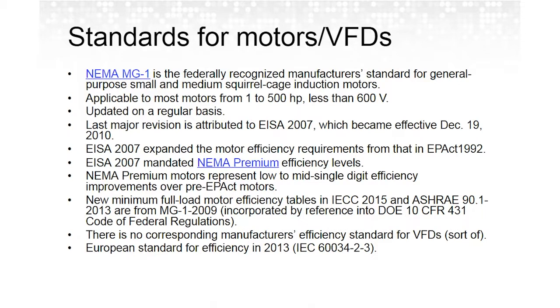Moving on to standards for motors and VFDs, let's put discussions about state energy codes aside and talk about motors and VFDs specifically. There is a manufacturer's standard called NEMA MG1, which is a federally recognized manufacturer standard for AC induction motors, and it's applicable from 1 to 500 horsepower for all motors less than 600 volts. The standard is updated on a regular basis. The most current version is 2016, which had relatively minor revisions. The big revisions to MG1 are attributed to the big changes in Energy Efficiency Acts, EPACT, and the Energy Independence and Security Act of 2007.